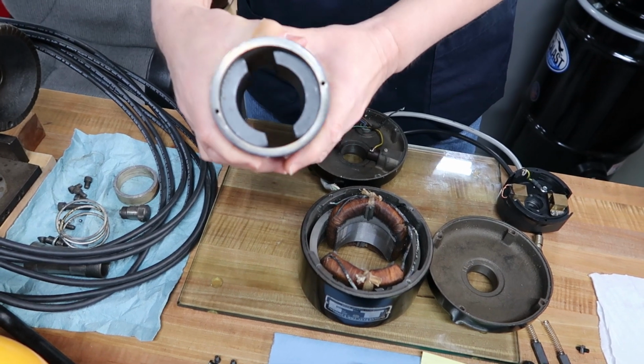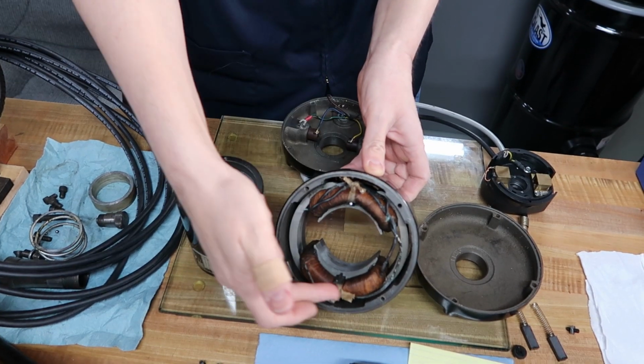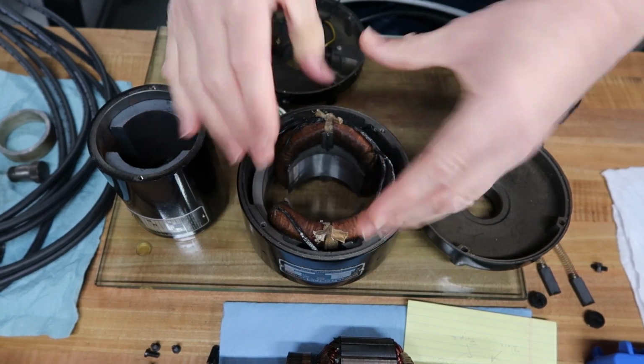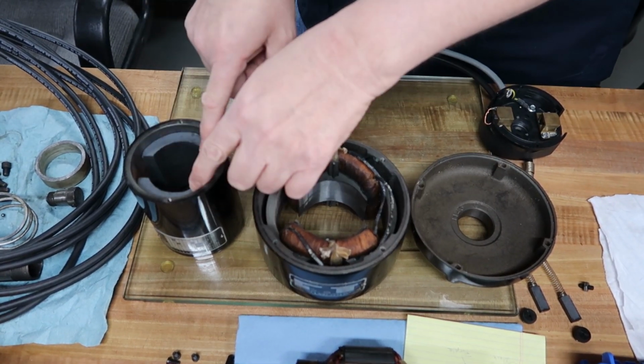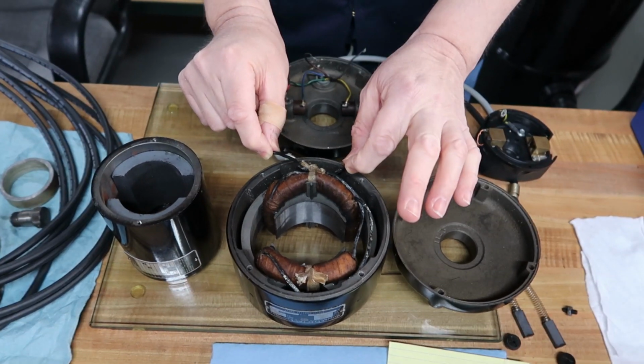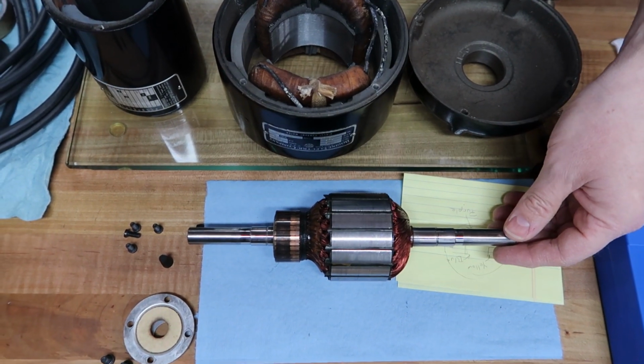You got that, Lance? Oh, yeah. As you can see, the older motor, a shunt wound motor, has field windings instead of magnets. There are 2 conductors for providing DC power, and that's how you create the field, kind of like a magnet. When powered, it looks like 2 magnets, just like here. In normal operation, this would take, I think, 100 DC volts, a constant DC voltage. For the armature, I believe it's 0 to 90 DC volts depending on the speed, with 90 volts being full power, full speed.